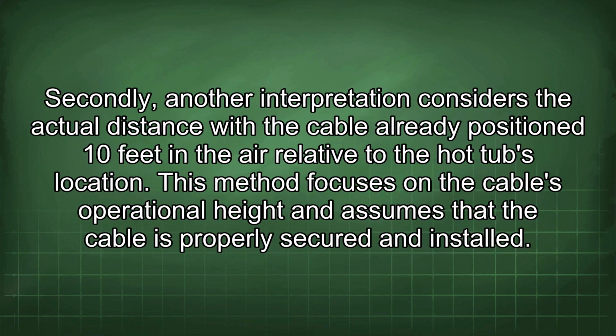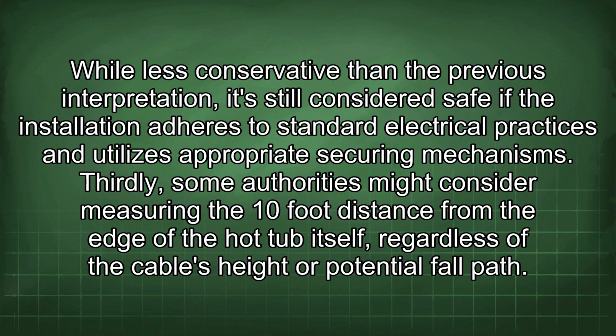Secondly, another interpretation considers the actual distance with the cable already positioned 10 feet in the air relative to the hot tub's location. This method focuses on the cable's operational height and assumes that the cable is properly secured and installed. While less conservative than the previous interpretation, it's still considered safe if the installation adheres to standard electrical practices and utilizes appropriate securing mechanisms.